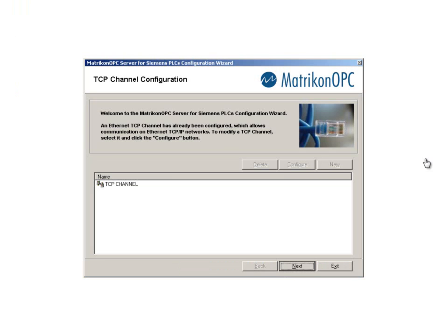If possible, please have your PLC connected to the computer at this point. Ensure that the computer is able to communicate with the PLC. The options are Ethernet connection to a supported interface card on the PLC, otherwise known as ISO on TCP, or by connecting to the MPI port directly on the PLC via Hilscher's Netlink to MPI port adapter.